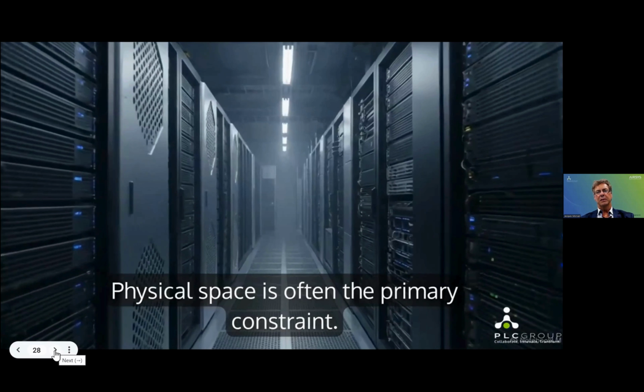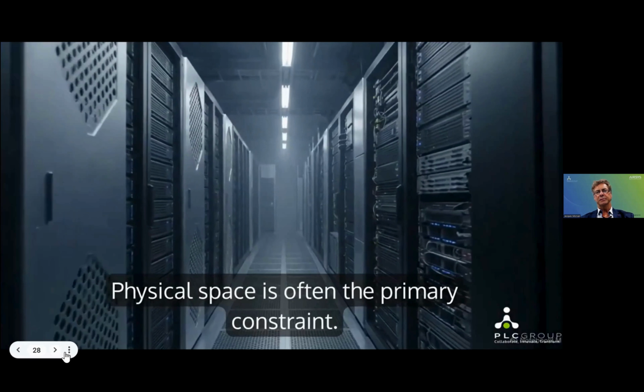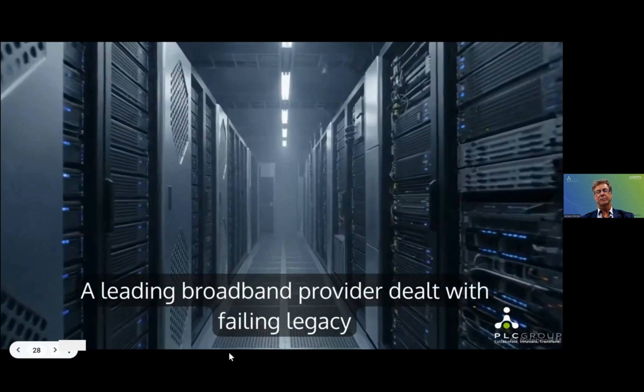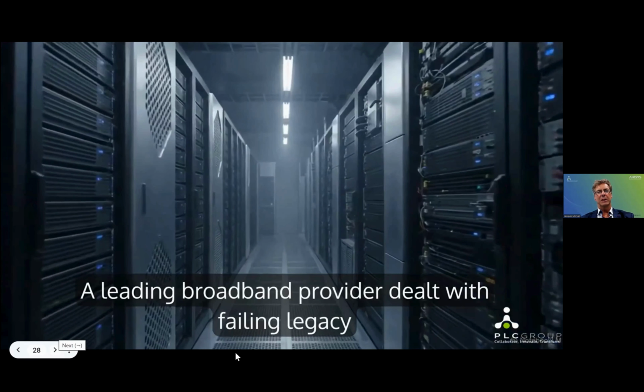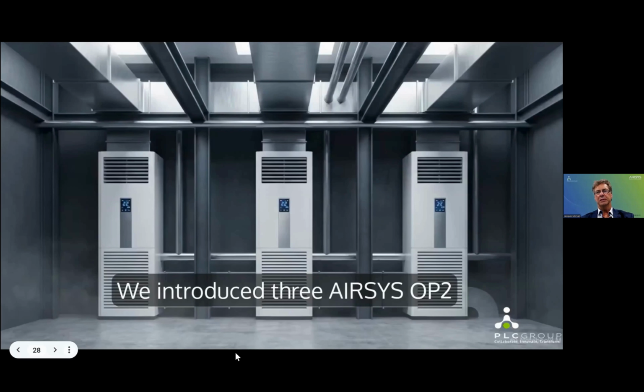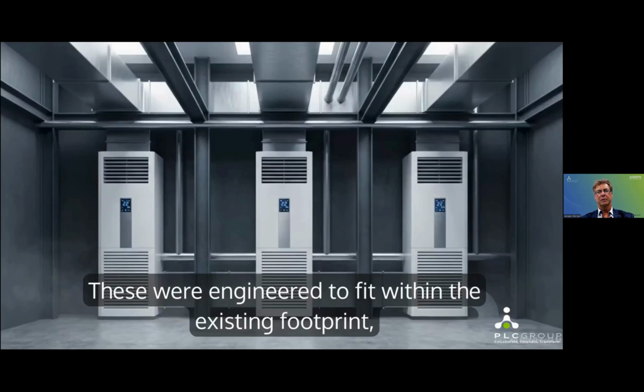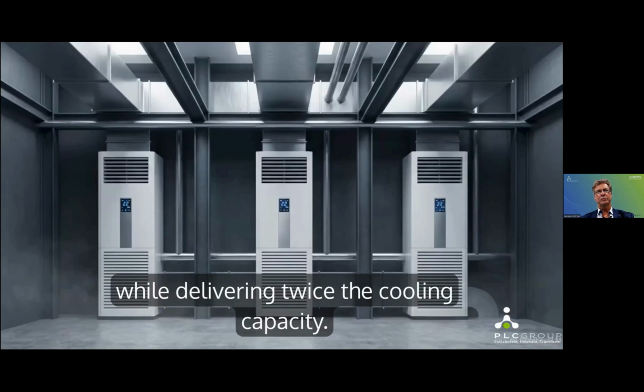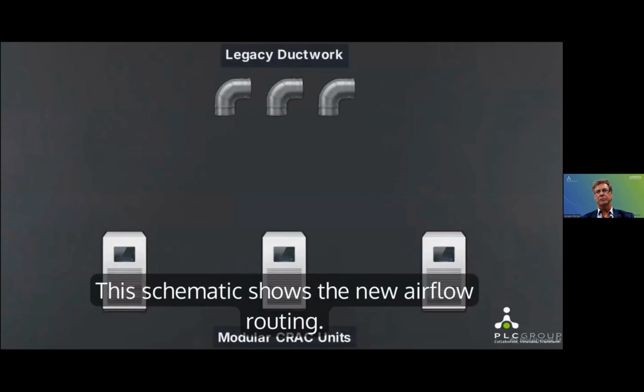Physical space is often the primary constraint. A leading broadband provider dealt with failing legacy cooling equipment trapped inside a cramped telecommunications Communications head-end facility. We introduced 3 AirSys OP2 40 kilowatt modular C-Rack units. These were engineered to fit within the existing footprint while delivering twice the cooling capacity. This schematic shows the new airflow routing.